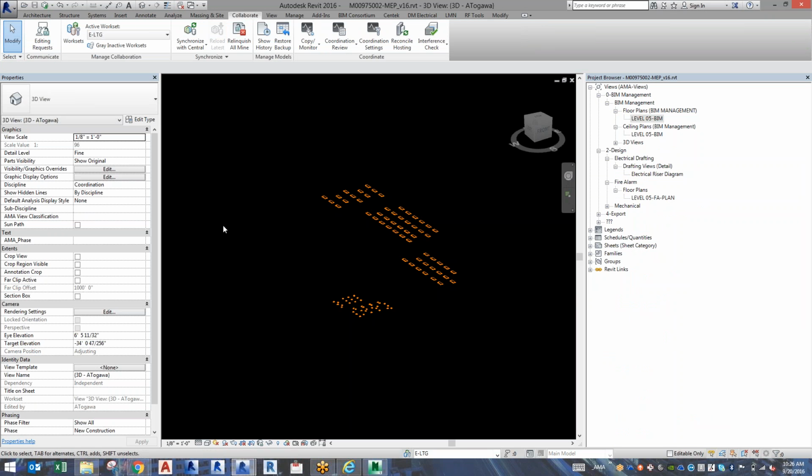I don't have it open, but they basically sent us all the families that they're using, and what we're going to do is we're going to load up our parameters and link them to the connectors for electrical fixtures and light fixtures. We send their model over to us, and we copy and monitor them. They'll come in with our own parameters already built in. So we can circuit, power up, and it'll work with our panel schedules. All of our shared parameters.